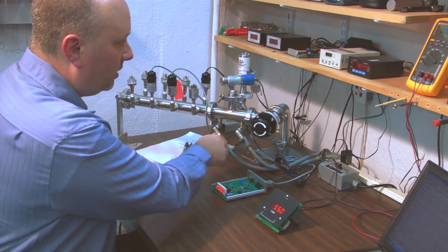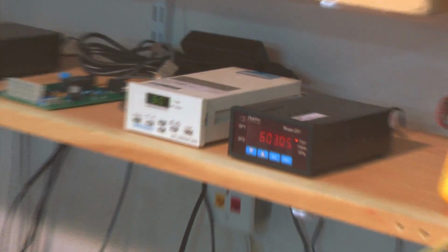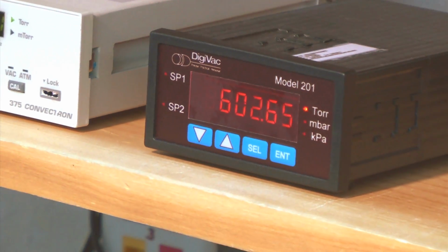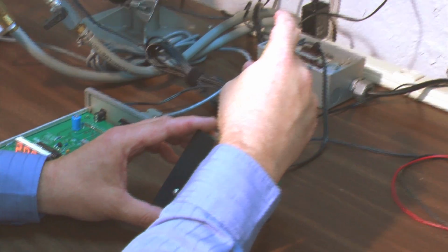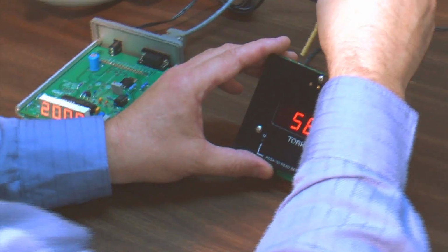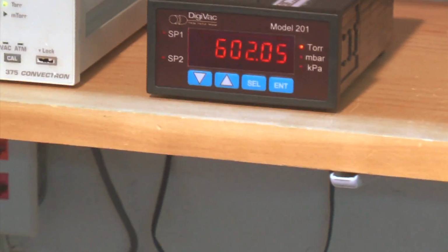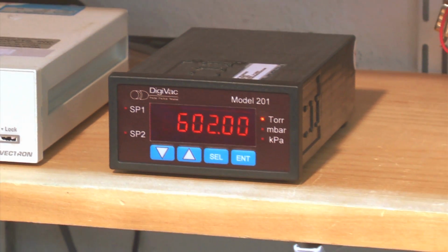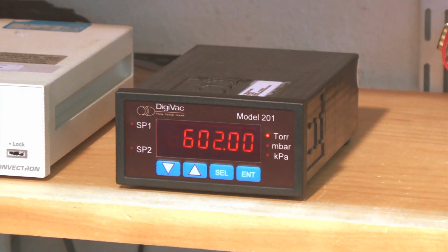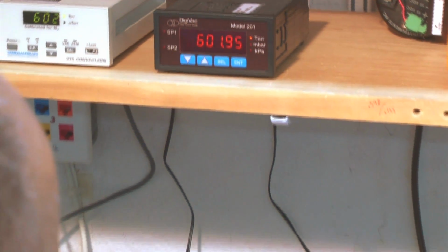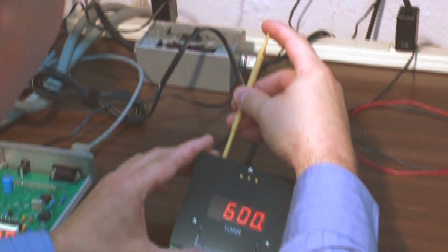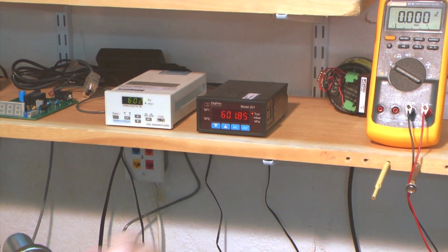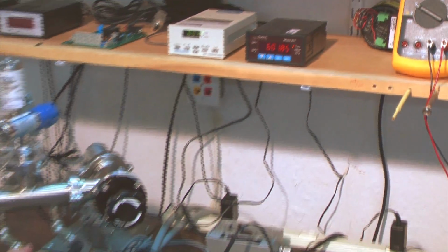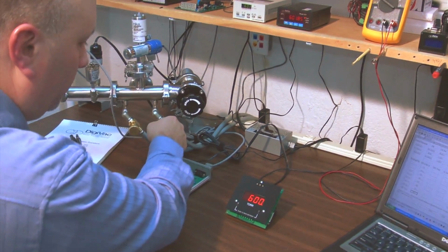We're going to take another reading at 600 torr. As I suspected, our readings have been a little low. We're going to make a secondary correction on our span using our Baratron indicating 600 torr, increase our gain by turning the atmospheric potentiometer clockwise. So we're right on the threshold of 600 torr. And now we're going to run backwards and take some readings decreasing vacuum. 600 torr, still 600.